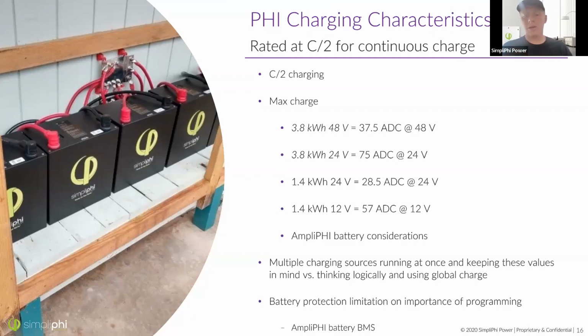So there's plenty of ways that you can figure out the maximum charge and discharge rate of the battery. And these are the continuous rates. This is not a surge capacity. When we compare this to something like a lead acid battery, lead acid are going to charge and discharge at around C/10, sometimes as low as C/20, and if you're really pushing it, maybe C/5.